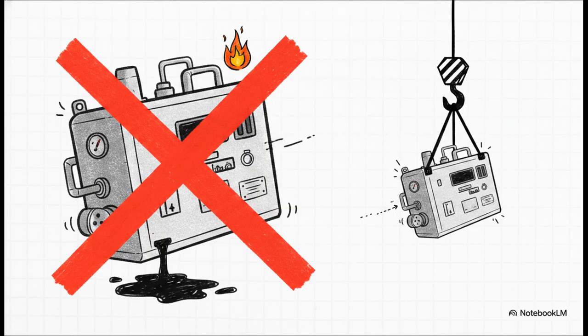Okay, before we wrap up, we really need to talk about the ghosts of the grid. Historically, a whole lot of switching relied on bulk oil volume-type circuit breakers. But let me be clear, the era of bulk oil is officially over. Because of the significantly higher fire risks and the heavy maintenance burdens compared to modern VCB or GIS alternatives, they have been completely phased out of Singapore's active standards. If you're on site today and you actually run into a bulk oil breaker, you are not looking at an active standard. You are looking at a relic that is slated for immediate replacement.